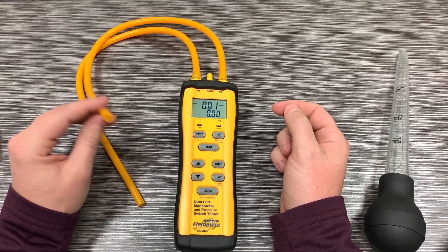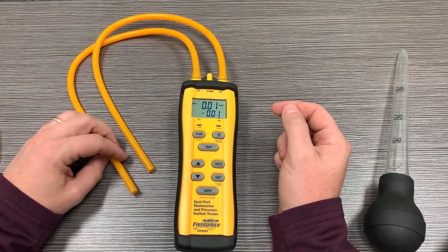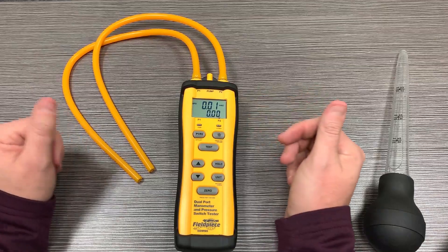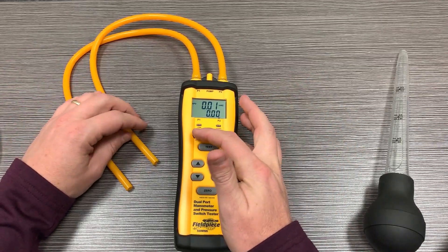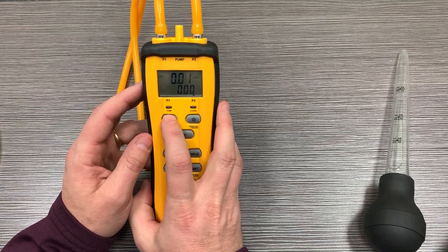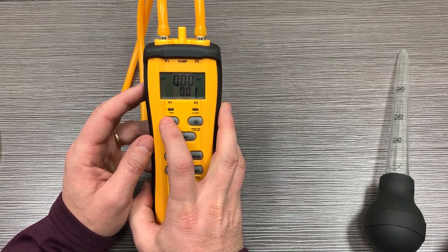So if I take one of them and put it in the return, and take the other and put it in the supply, that bottom number is going to represent the differential between both, whereas I'm going to see the individual ones as I toggle back and forth between P1 and P2.